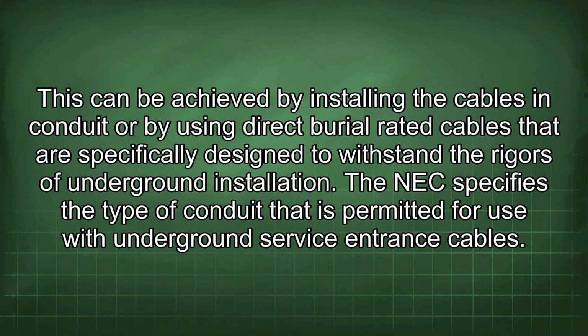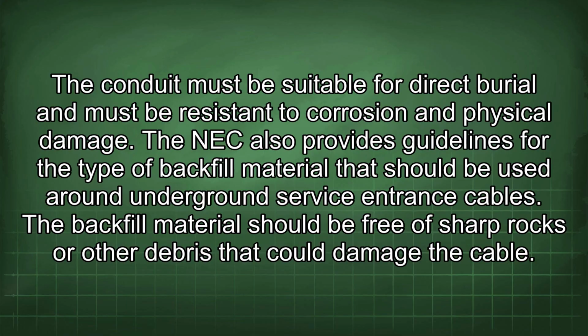This can be achieved by installing the cables in conduit or by using direct burial rated cables that are specifically designed to withstand the rigors of underground installation. The NEC specifies the type of conduit that is permitted for use with underground service entrance cables. The conduit must be suitable for direct burial and must be resistant to corrosion and physical damage. The NEC also provides guidelines for the type of backfill material that should be used around underground service entrance cables. The backfill material should be free of sharp rocks or other debris that could damage the cable.